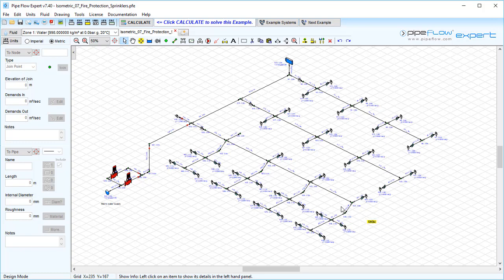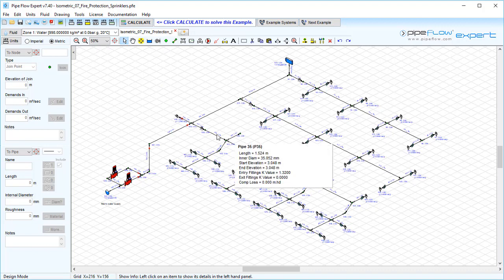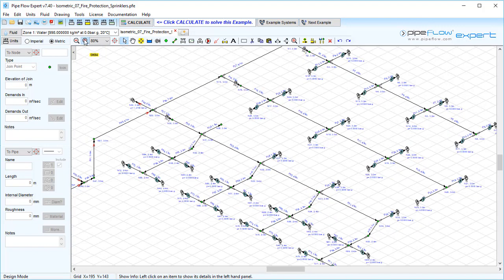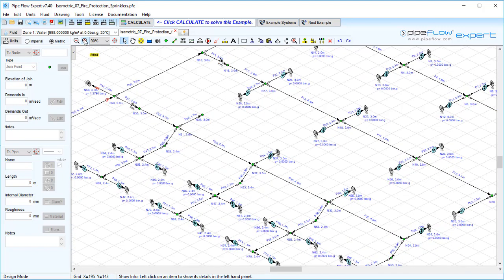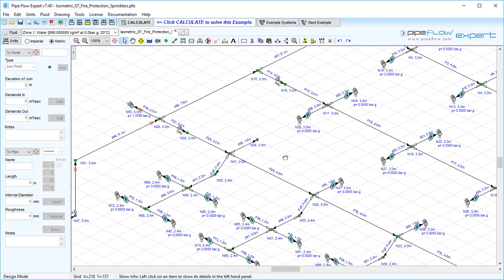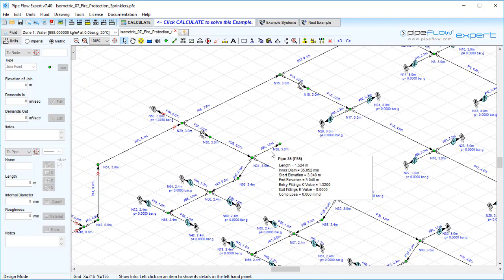When modeling a spray nozzle in Pipe Flow Expert, a combination of the component and an end pressure node can be used to model the performance. Where the flow will discharge to the atmosphere, it is usual to use the flow versus pressure loss characteristic of the spray nozzle to establish the flow leaving the system due to the pressure differential across the nozzle.